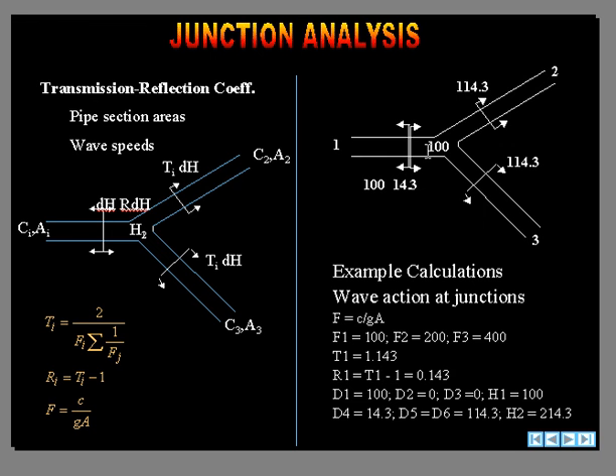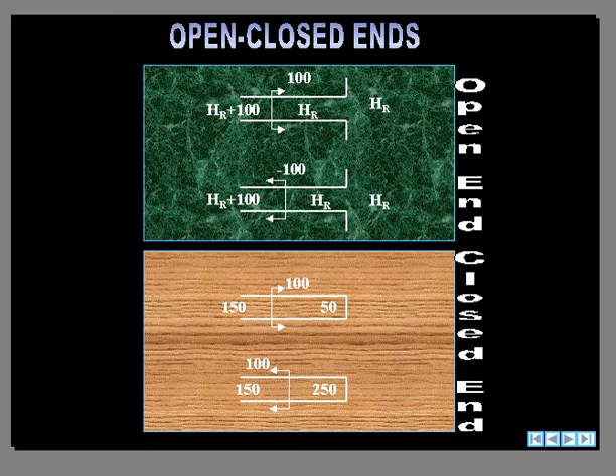Open and closed ends are sort of special cases. A wave at an open end is reflected negatively. A wave at a closed end is reflected positively. Both of these have a profound effect on the transient response. Closed ends, because of the positive reflection, can increase pressures even further in a pumping system.